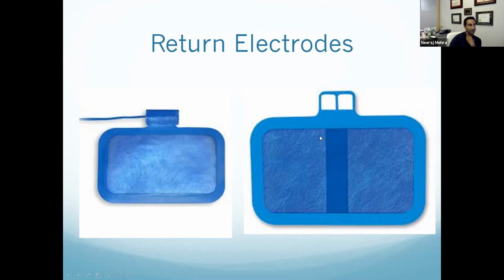And the safety feature that's in the pads now, in the return electrodes now, is the better term, is that they have these dual sides with this non-conducting strip in the middle. So if you ever look at this, you'll see this. And when you're using this return electrode, both sides here have to be in contact with the patient. The return electrode says, I want energy coming back from both sides. Otherwise, that tells me that you have enough surface area in contact and that you have low current density going through here. And so that you're not going to get a site burn. So it's more of a historic thing and safety thing, but that's where this thing comes from.